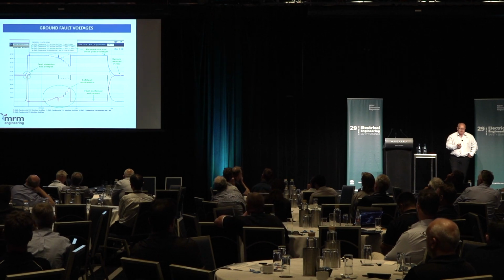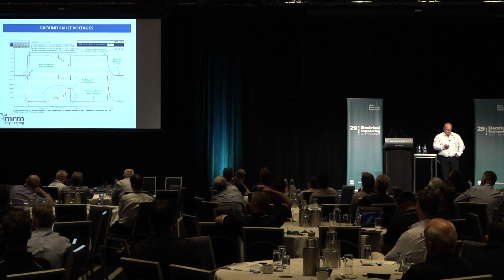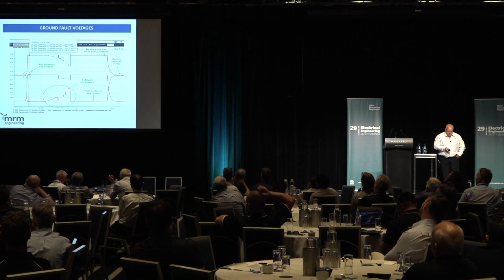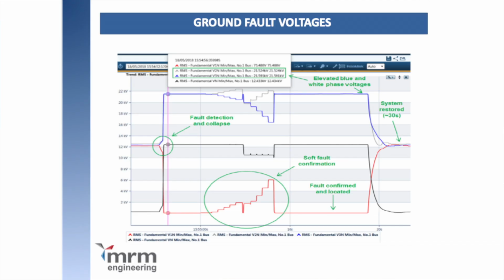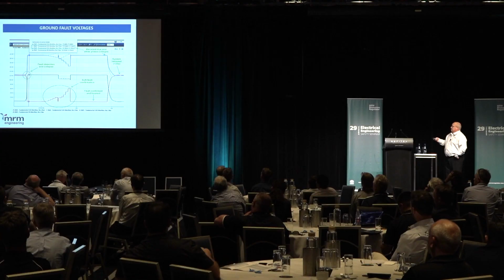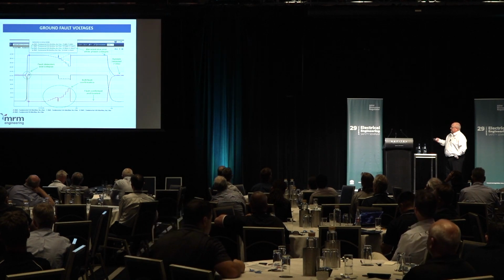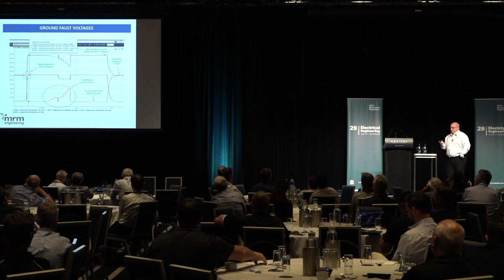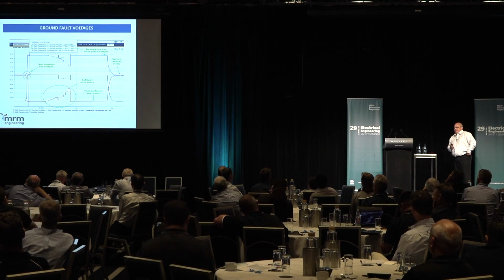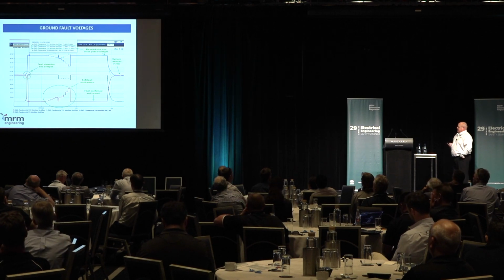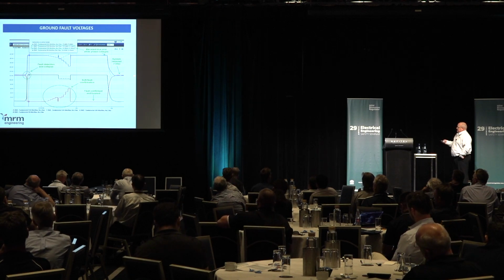So this is the sample test they did at Kilmore substation in Victoria. So on the diagram you can see we're operating here at 12 kV. One of the lines, the red line, goes down, hits earth, and the corresponding phase to earth voltage then rises on the other lines up to 22 kV roughly, which is the standard typical thing you would see in an IT earthing system where you've got a phase to ground earth fault. The insulation levels have to be increased. And then once the fault gets cleared, the system turns back to normal.